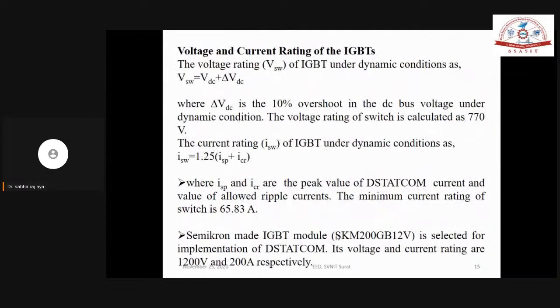Okay. How can we select the IGBT current and voltage rating? You can take the DC link voltage plus some percentage of overshoot. So 700 plus 10%, if you have taken, so 770 you can take. But again, it depends upon the market also. Maybe the cost of an 800 volt IGBT and a 1000 volt IGBT is nearby only. In that case, maybe you can take 1000 volt. Also, maybe we will not get an 800 volt IGBT. In that case, a round figure rating you can take. Maybe 1000, maybe 1200, depending upon their design.